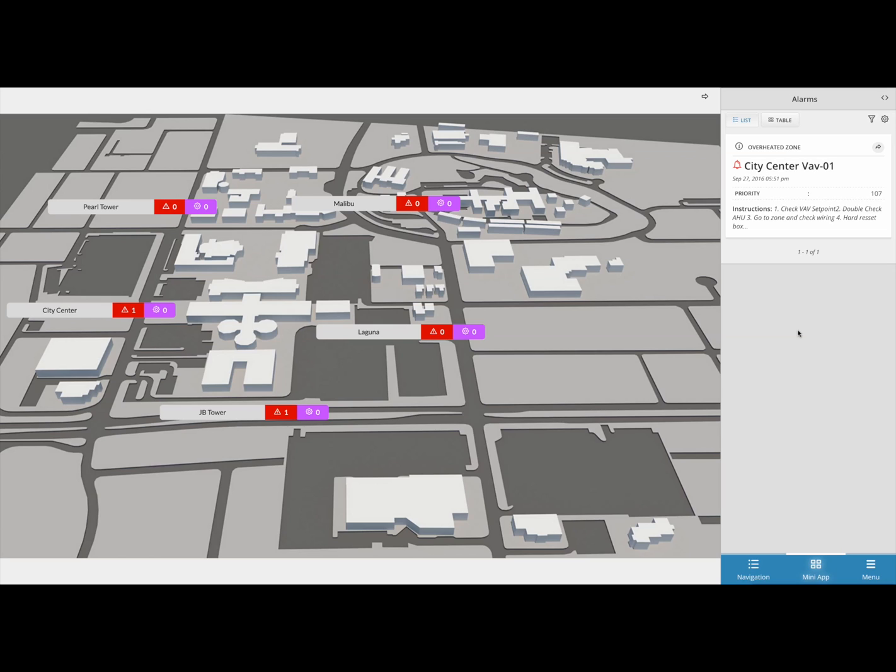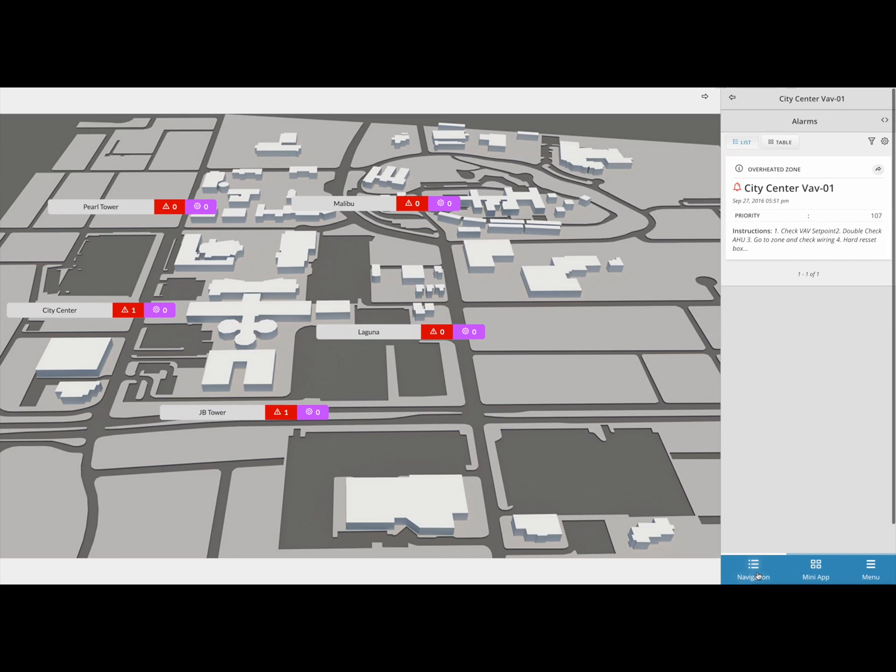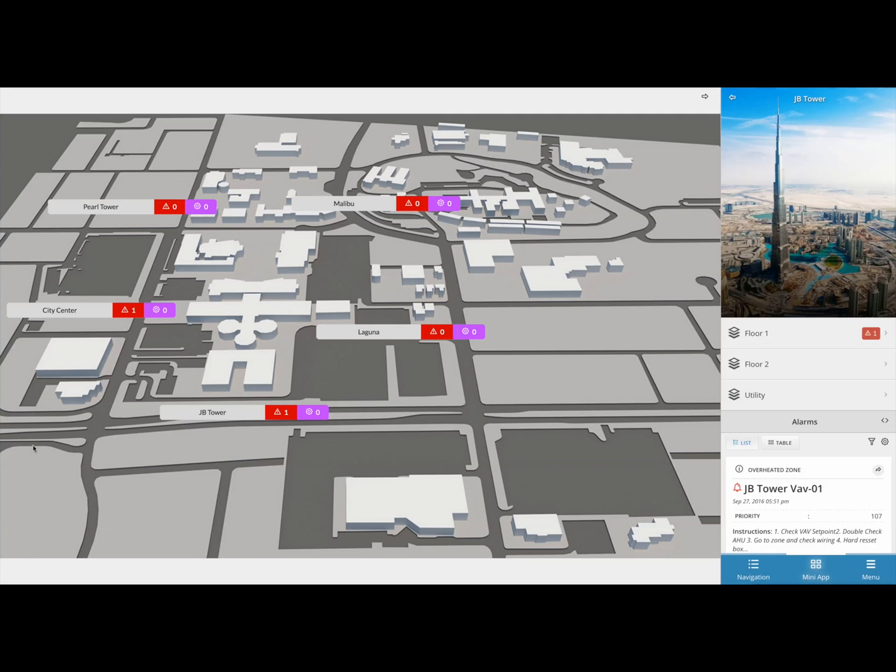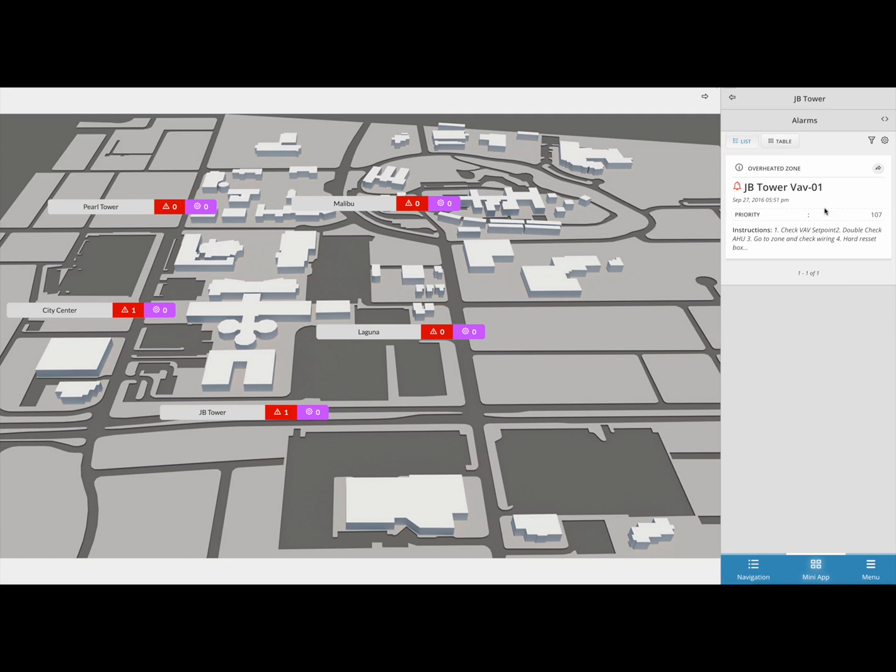If you recall from an earlier step, the program we created was running on not just one equipment but was actually running on multiple equipment that shared the same tags. So if you look at our campus graphic, we can see that an alarm was thrown in the JB tower site as well. If I dig in further, we can see exactly which VAV threw the alarm.